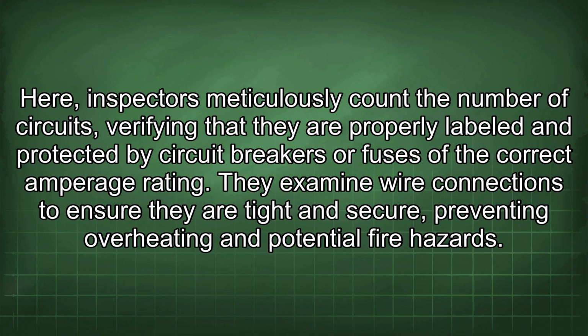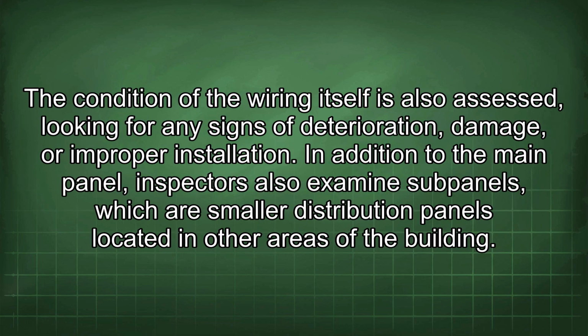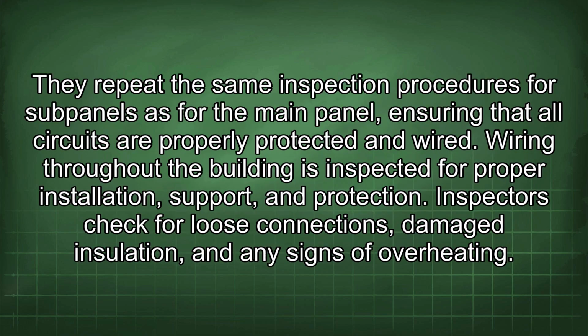They examine wire connections to ensure they are tight and secure, preventing overheating and potential fire hazards. The condition of the wiring itself is also assessed, looking for any signs of deterioration, damage, or improper installation. In addition to the main panel, inspectors also examine subpanels, which are smaller distribution panels located in other areas of the building. They repeat the same inspection procedures for subpanels as for the main panel, ensuring that all circuits are properly protected and wired. Wiring throughout the building is inspected for proper installation, support, and protection.